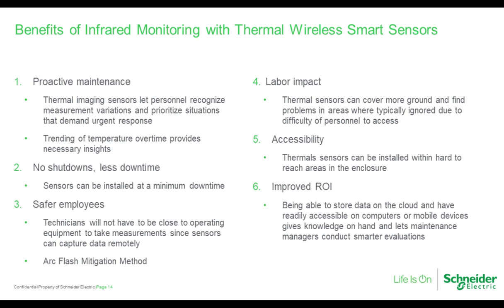Trending of temperature over time provides more insight from everything you can gather with that data to make future decisions based on what you're seeing and trending. Also, there are no shutdowns and less downtime; sensors can be installed with minimum downtime. And these sensors can be put into places where thermographic windows cannot be used, such as sometimes main bus and medium voltage switchgear, or low voltage bus and low voltage switchgear, where the windows can't penetrate some of the barriers and look at joints within those barriered off pieces of equipment or bus. So these thermal sensors can be put into all kinds of different locations and fed back through a system so that you can collect the data. Those are a nice addition to digital information and predictive preventative maintenance for the future.